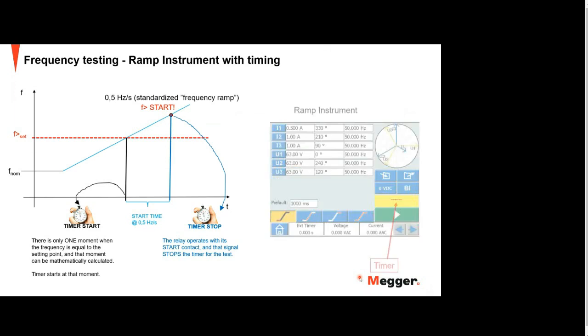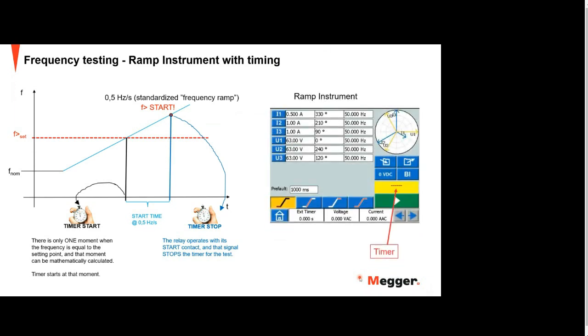So this is the recommendation from this standard, how to do a frequency change. You shall do it in the ramp instrument to make a ramp, and you shall not do it as a sudden change like pre-fault fault. So that's the common recommendation here. And if you are using the Sverker 900, you have the possibility in the ramp instrument. You set the ramp and run it, and then you have the possibility to measure the time. So it's very easy to do this in the ramp instrument with the Sverker 900.